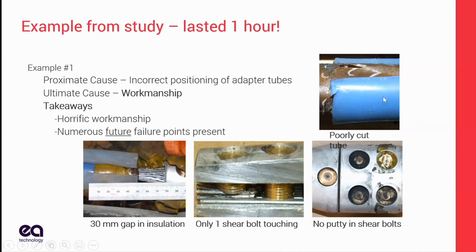Tubes were cut badly. Insulation was lots of workmanship issues. I use the term horrific. It was horrific. And, you've got to address these sort of issues. Fixing one of them or two of them would have still led to failure.